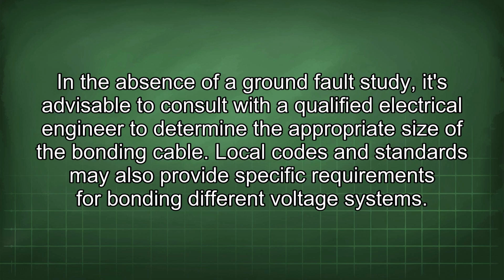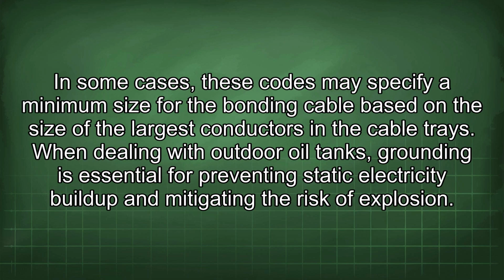Local codes and standards may also provide specific requirements for bonding different voltage systems. In some cases, these codes may specify a minimum size for the bonding cable based on the size of the largest conductors in the cable trays.